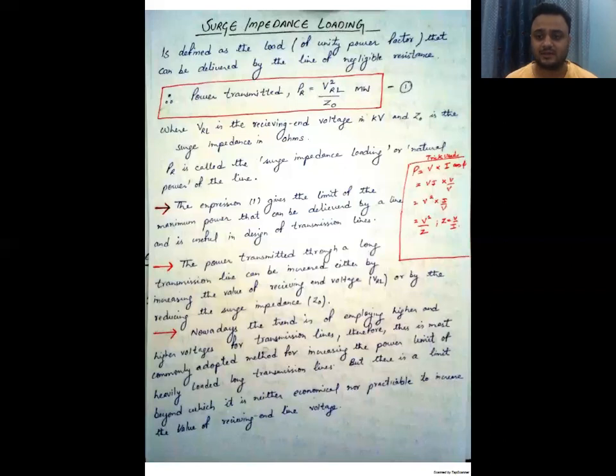That formula can also be converted and written as the ratio of the square root of the line inductance to the shunt capacitance, which can also be referred to as the surge impedance formula.